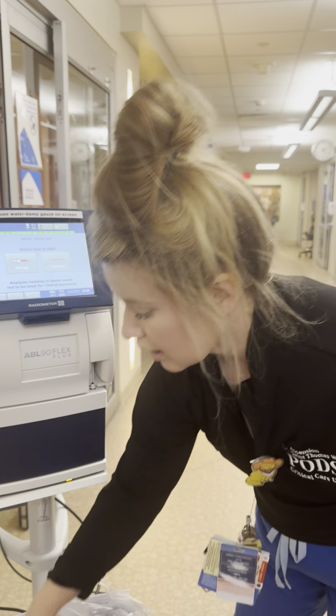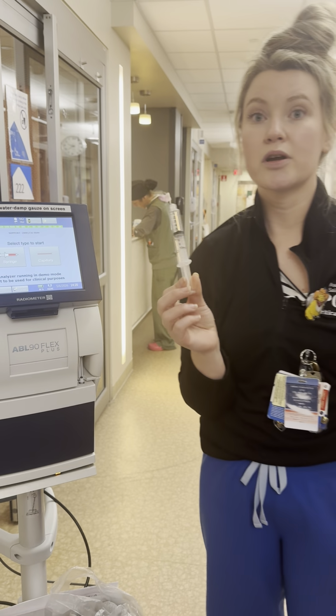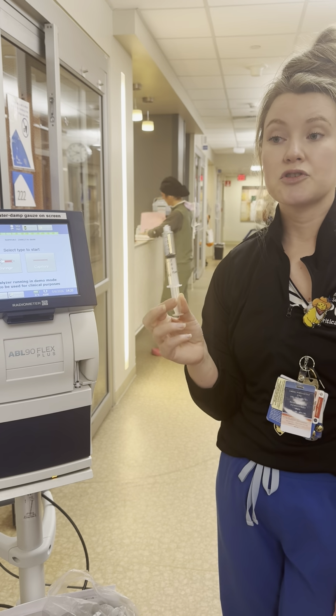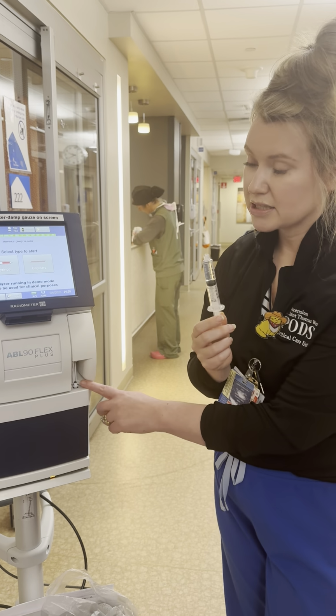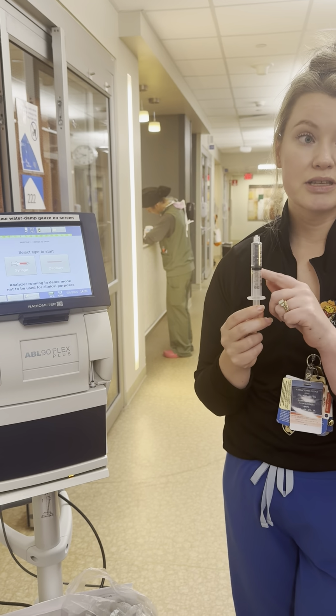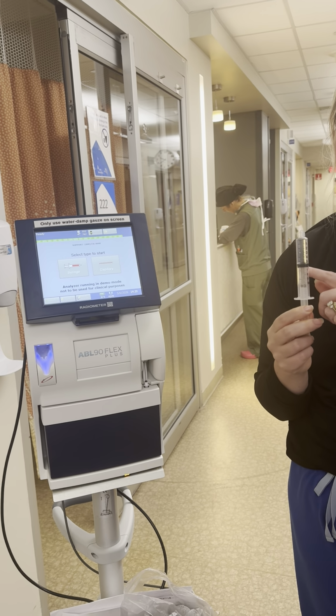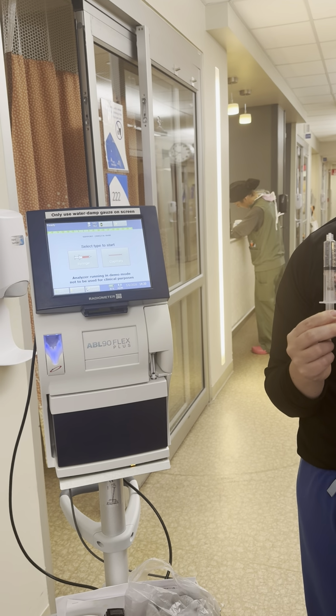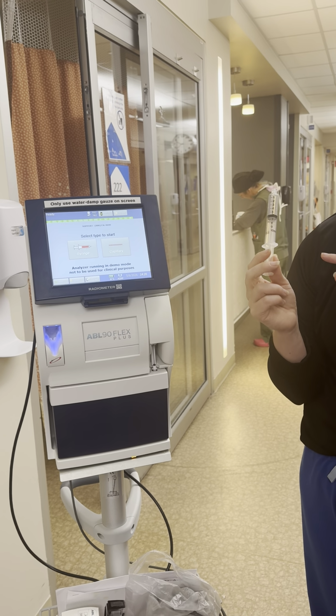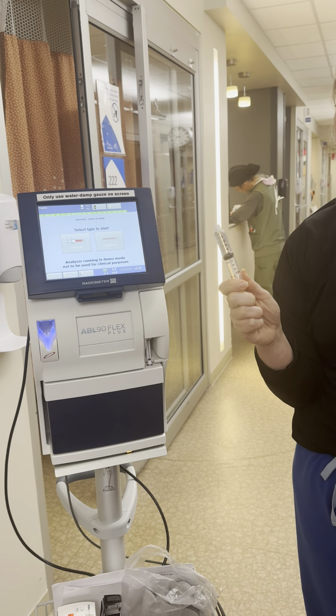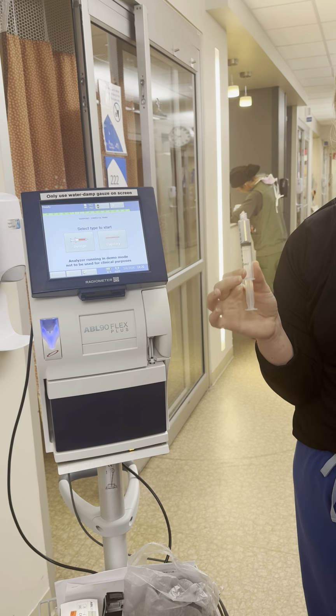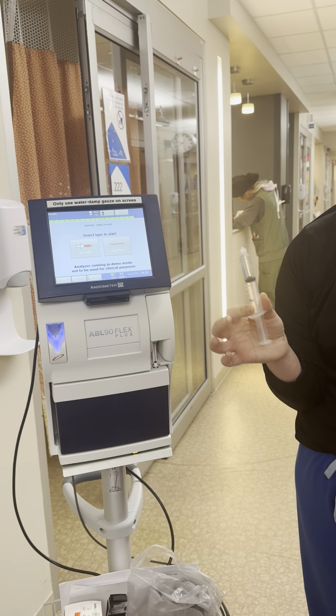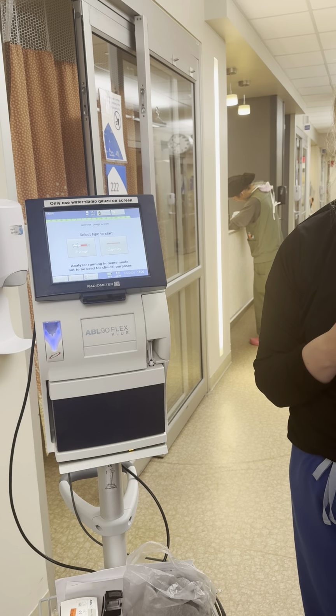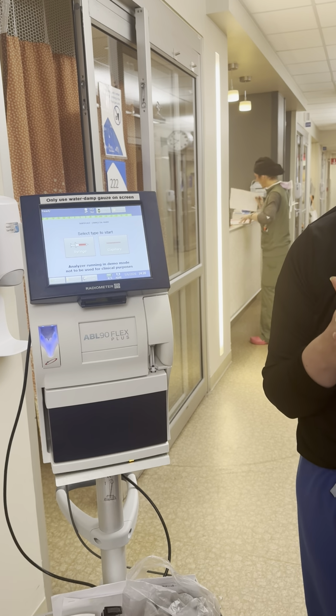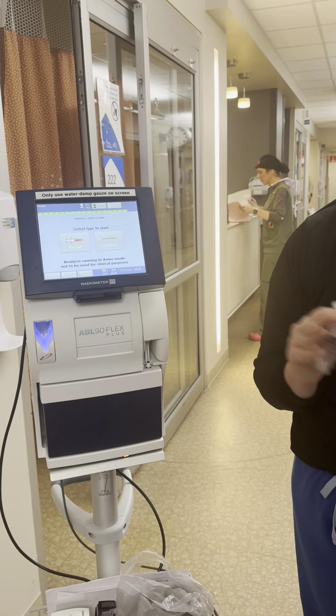So you're going to have your sample drawn into a heparinized syringe. You have to draw at least 1 ml. So this probe has to have room to be able to drop down into your syringe. The sample size is only about 0.1 ml. We're only using heparinized syringes. When you draw it, you are going to remove all of the air. It does have a cap. You can put the cap on first before you de-air it so you don't make a mess. But you're going to spin it like you're supposed to with the iStat. With the heparinized syringes, you do have to spin for at least 10 to 15 seconds. So you'll spin it, and then you're ready to go.